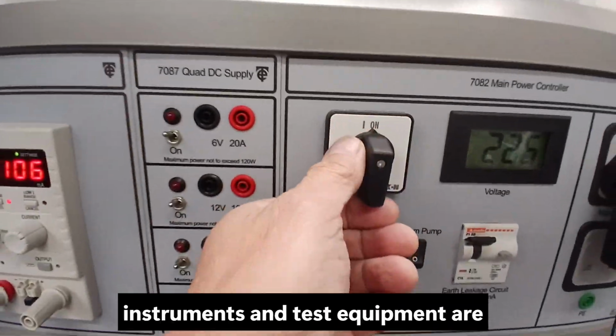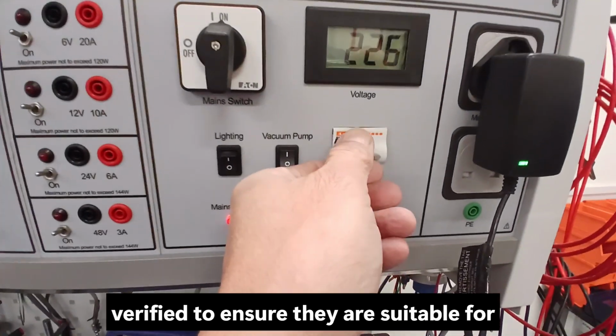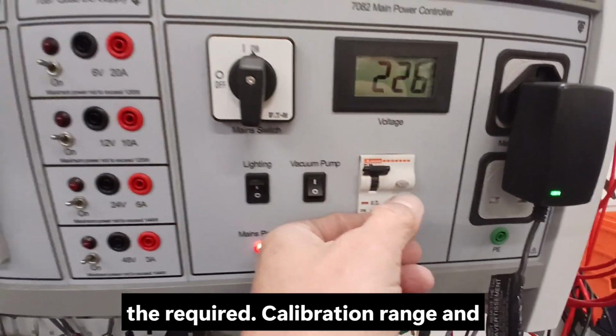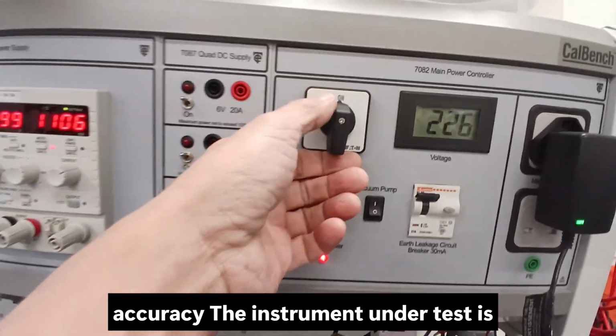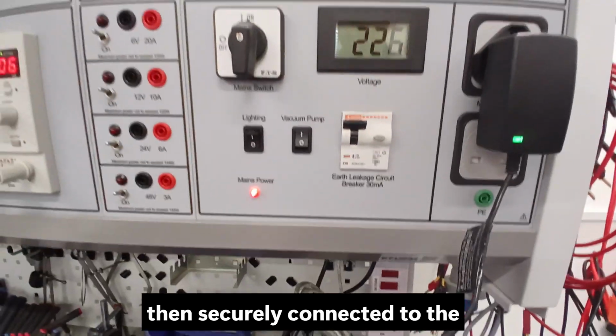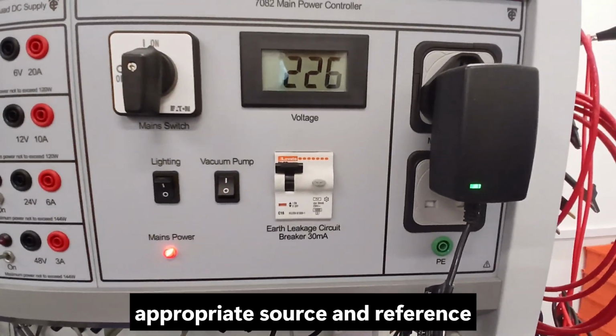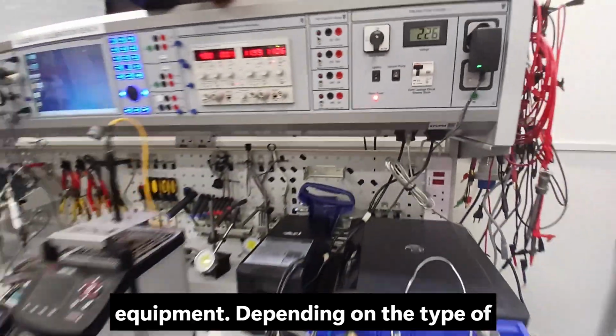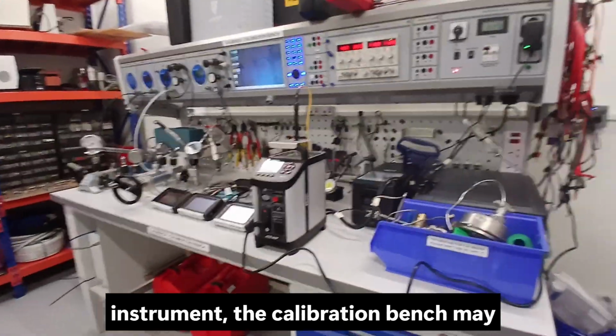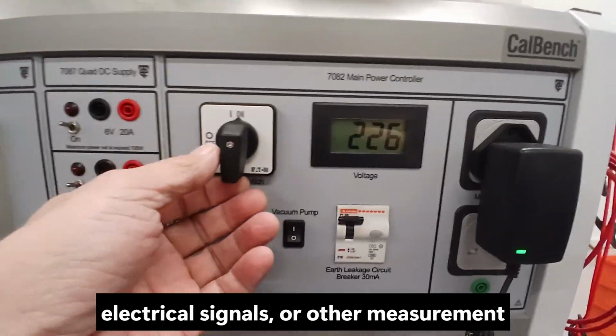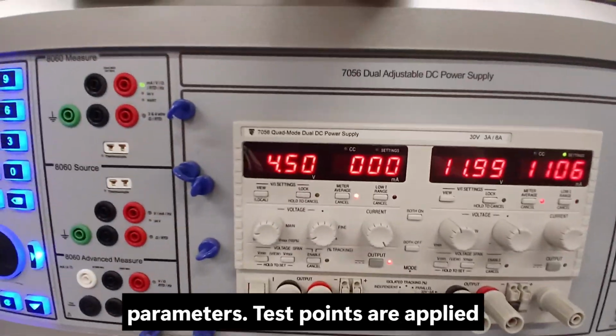The reference instruments and test equipment are verified to ensure they are suitable for the required calibration range and accuracy. The instrument under test is then securely connected to the appropriate source and reference equipment. Depending on the type of instrument, the calibration bench may provide control pressure, temperature, electrical signals, or other measurement parameters.